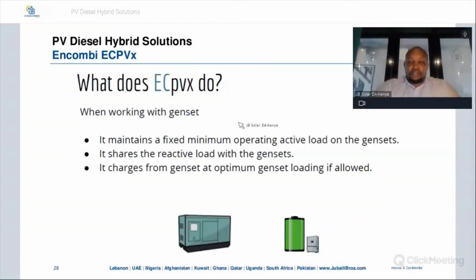When working with the generator, what does the fuel safe controller do? So it maintains a fixed minimum operating load on the generator. We had seen earlier that operating below the minimum rated load is going to be detrimental to your diesel generator, and you want to extend the lifetime of your diesel generator. So with the integration of the fuel safe controller, you're making sure that your generator is operating above the minimum rated load, and it shares the reactive load with the genset, again making sure that you have good power quality. And it also allows charging the battery from the generator if that setting has been put in. So in this case, with the fuel safe controller, you can charge your battery system from the grid, as we had seen earlier, or from the diesel generator.